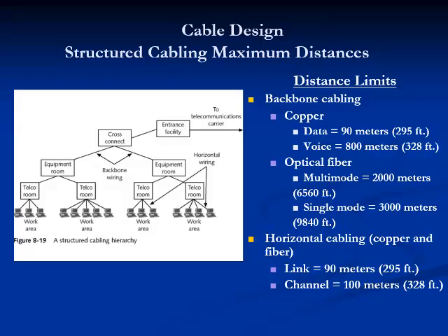Also, regarding cable design, please recall from Module 1 the maximum cable lengths, depending on whether they are used in the entrance facility, equipment room, telecommunication room or work areas. The distance limits mandated by the standards for copper cable in the backbone that uses data applications is 90 meters or 295 feet, and for voice applications it's 800 meters.